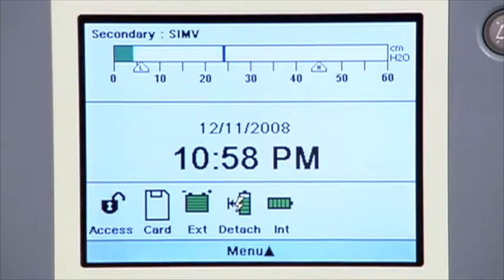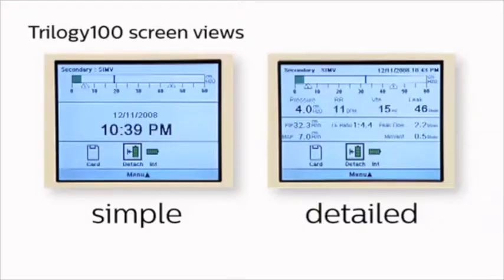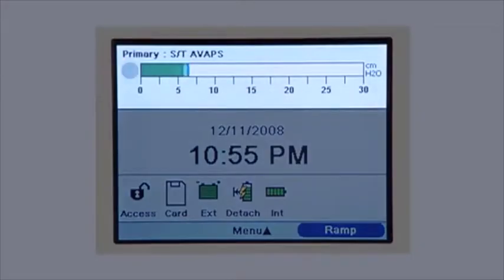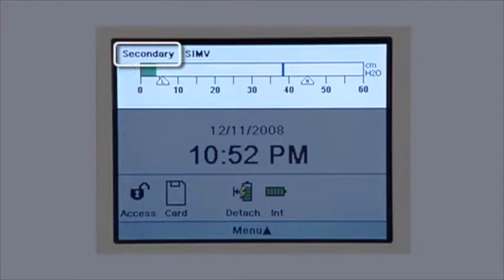The appearance of this screen may vary depending upon how your clinician has set up your device. Trilogy 100 has a simple and a detailed screen view. On the simple display screen, the top section is called the monitor panel. It shows which of the ventilator's many therapy modes is in use. If any special features are active, an indication will appear beside the therapy mode. If the physician has ordered 2 different prescriptions, for example, one setting for daytime and another one for nighttime, you will see primary and secondary indicated.